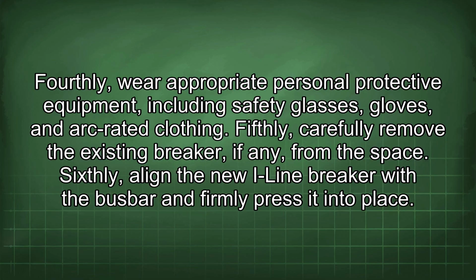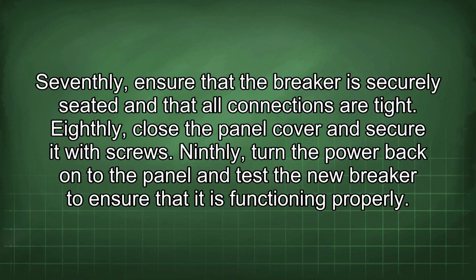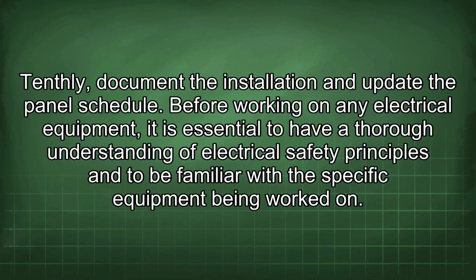Fifthly, carefully remove the existing breaker, if any, from the space. Sixthly, align the new I-Line breaker with the busbar and firmly press it into place. Seventhly, ensure that the breaker is securely seated and that all connections are tight. Eighthly, close the panel cover and secure it with screws. Ninthly, turn the power back onto the panel and test the new breaker to ensure that it is functioning properly. Tenthly, document the installation and update the panel schedule.